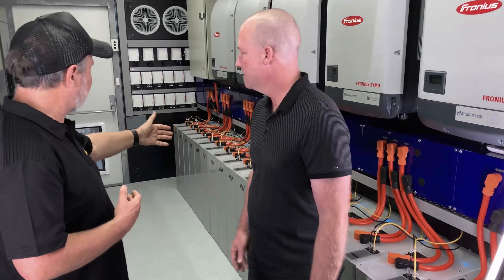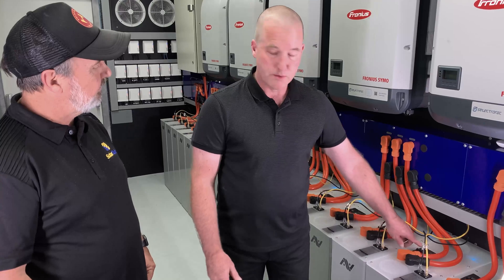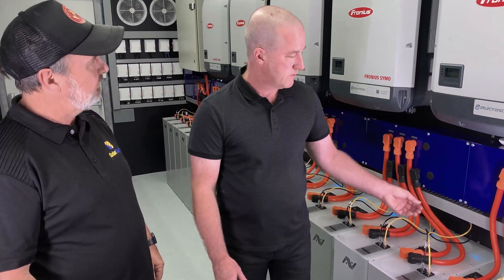I noticed there's a lot of cables and wires looking down here — what's all this about? So each of the batteries has its own ethernet port and we actually power the communications to the battery. Every battery has its own cooling fan as well, so if we want to run really high powered modes we can blow fresh air through the battery. We've got an alarm wire here as well. Let's just say there was a fault somewhere and the inverter was overcharging the cells because someone programmed it incorrectly, and then the comms went off because lightning hit and took them out — each battery can still send a control signal to the inverters to turn off directly as a manual signal, independent of comms. Additionally, if that failed and the inverter still didn't turn off and kept charging, the battery can trip itself off the battery bus duct if any cell goes over the voltage allowed — it automatically throws the circuit breaker. So it's got intrinsic safety and multi-levels of fail, with dual redundancy for everything: cooling, lighting, battery power, energy — everything.